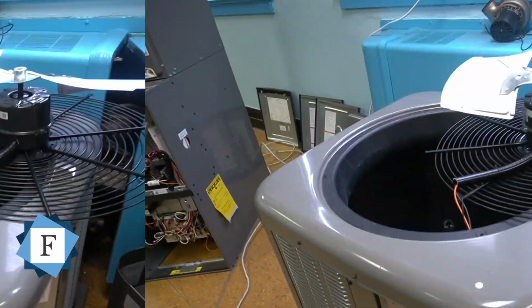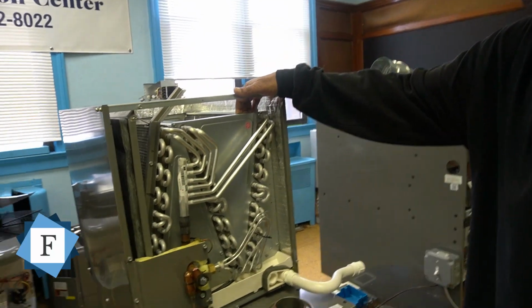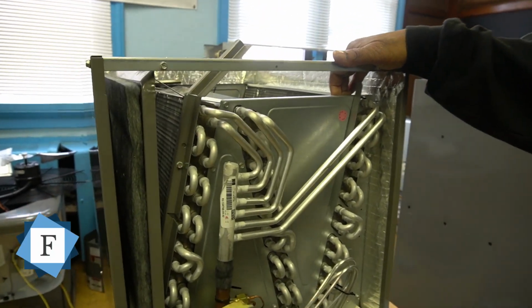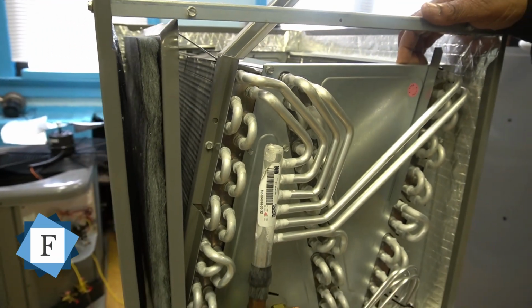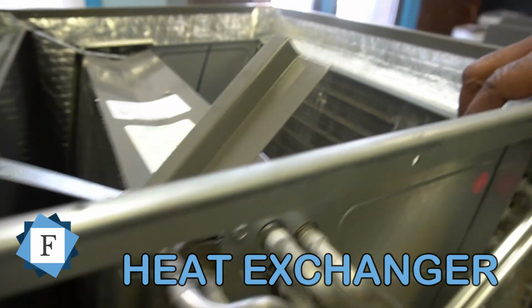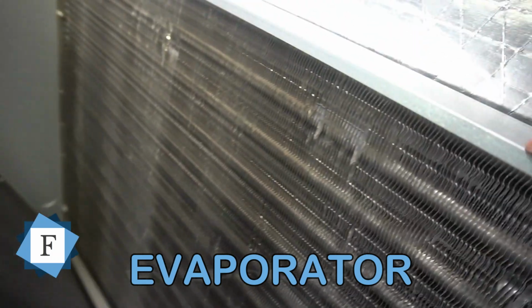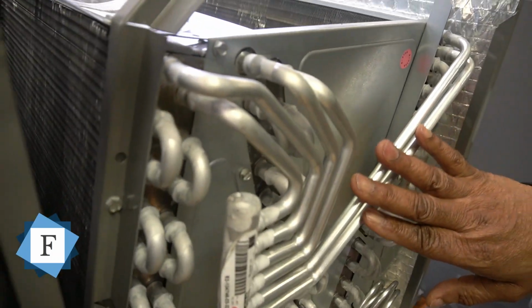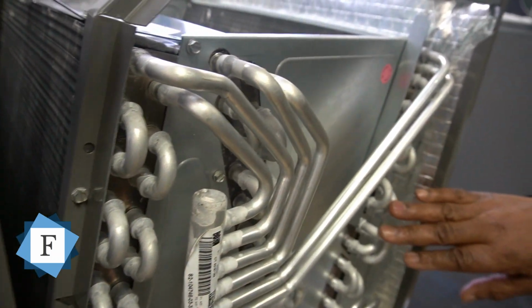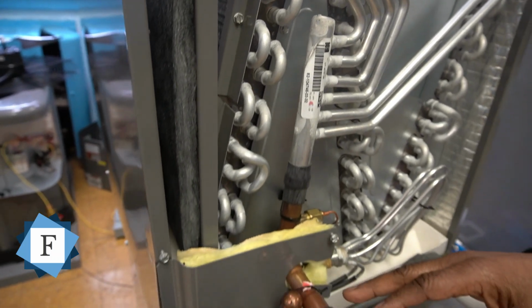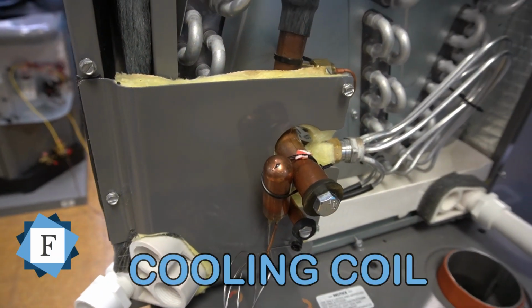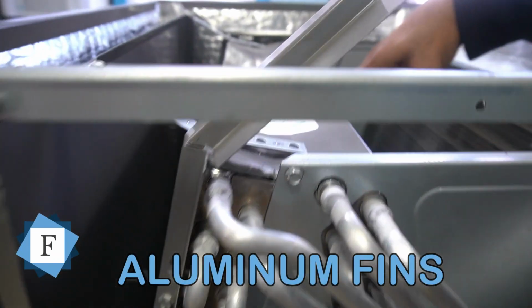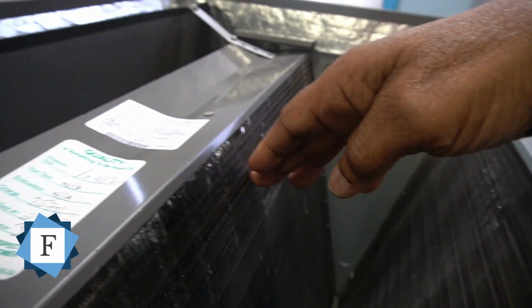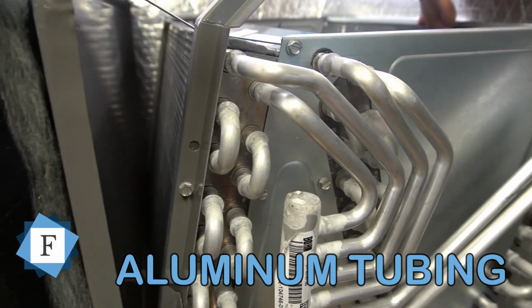Okay, now let's go inside. Okay, now we're inside. This device here is located inside your furnace, and this is called a heat exchanger. And this heat exchanger is defined as an evaporator. Okay, and as you can see, we have aluminum coils on our evaporators. Most of what you see are copper tubing, but this is aluminum. But the evaporator, also called the cooling coil. These are the aluminum fins that make up the evaporator, and this is our aluminum tubing that makes up the evaporator as well.